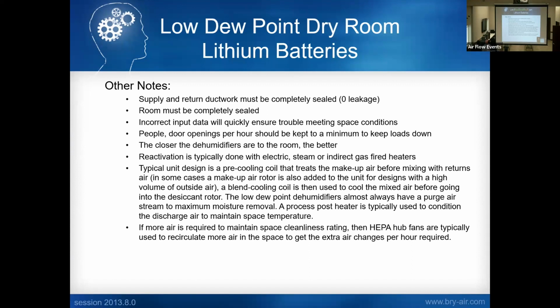So to prevent any last minute problems, like the unit's not working, what do we have to do? Well, you have to put a vapor barrier up. It's good to make a site visit and get photos if you can of pipe penetrations and conduit penetrations. If you see openings, take measurements, because we can design a unit to probably handle it if we know the space is not sealed up at all. Vapor barrier, we can design a unit for that, versus a tightly constructed room. Again, you're going to pay more for the equipment because you have to oversize it to make up for those openings.